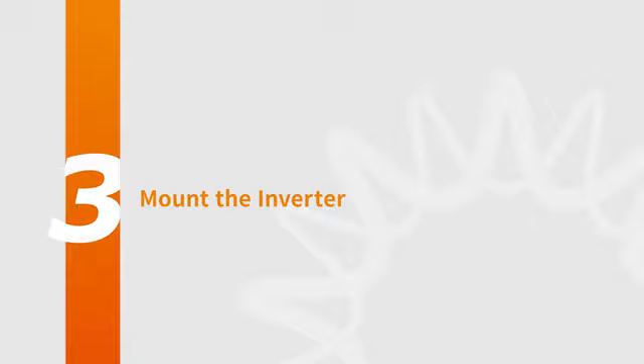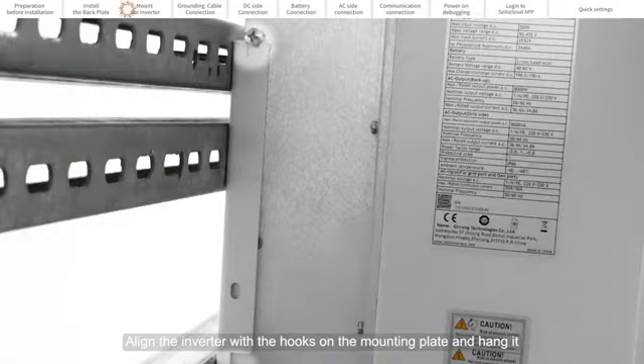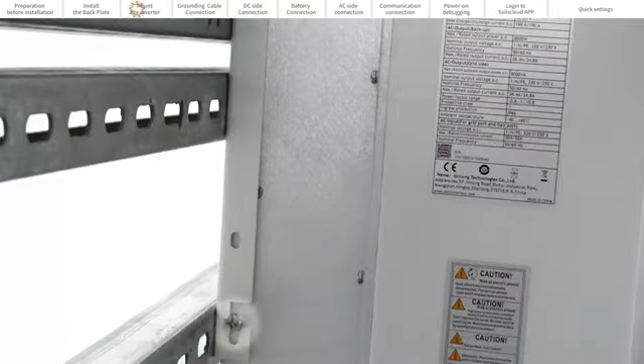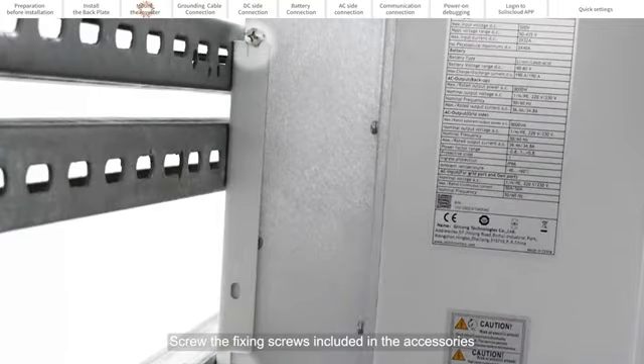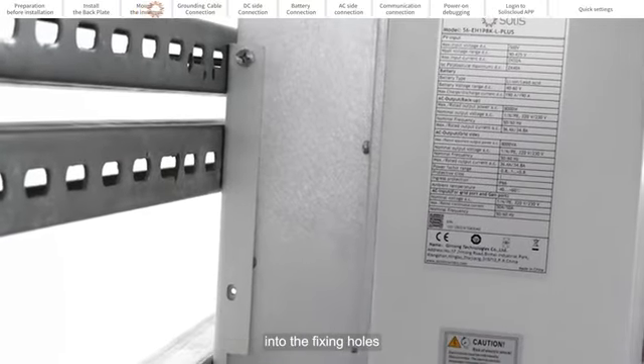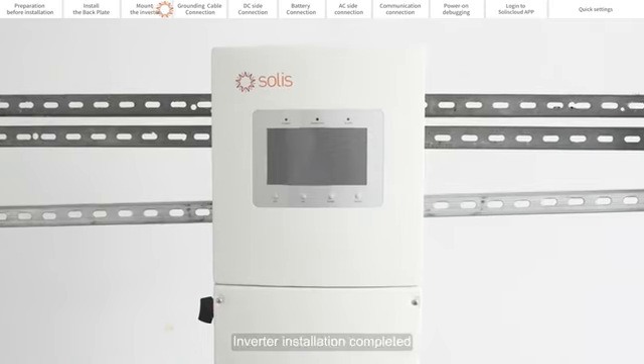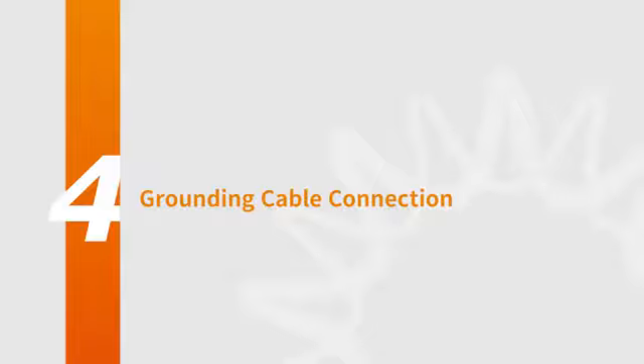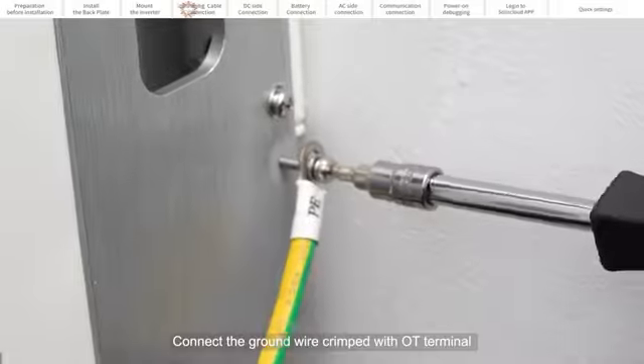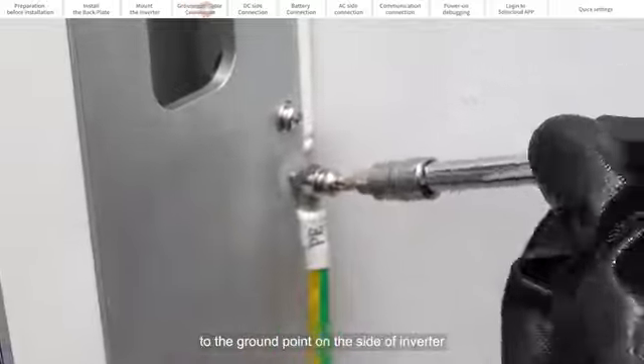Part 3. Mount the inverter. Align the inverter with the hooks on the mounting plate and hang it. Screw the fixing screws included in the accessory bags into the fixing holes. The inverter installation is complete. Part 4. Grounding cable connection. Connect the grounding wire crimped with an OT terminal to the ground point on the side of the inverter.